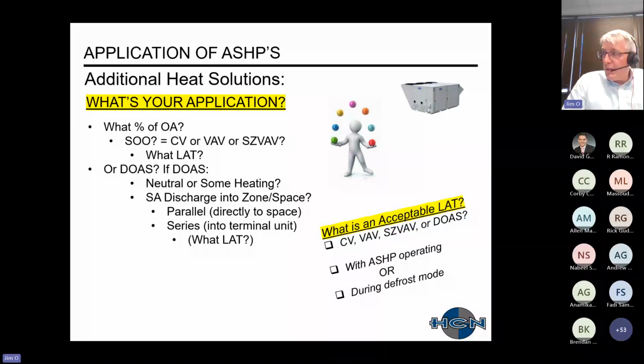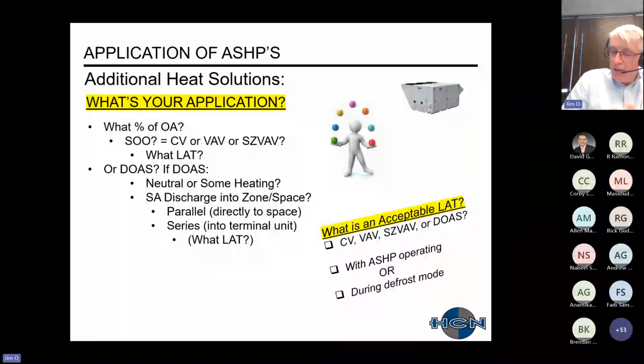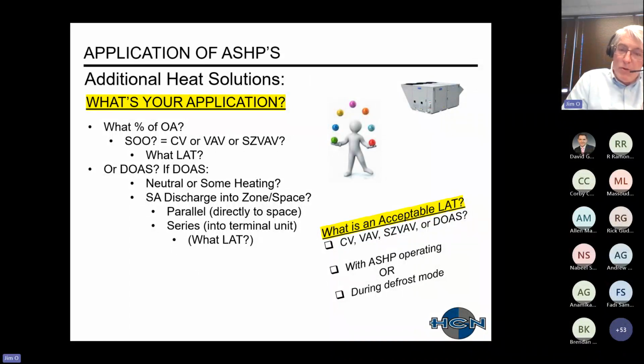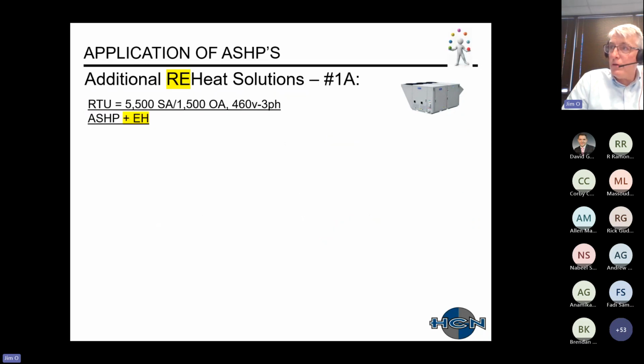All right, so what's an acceptable leaving air temperature? Once again, dependent on your system. What I want you to understand is what's the leaving air temperature that you're getting from your rooftop unit when your air source heat pump is operating, and then also when your air source heat pump is not operating, which would happen during defrost mode.